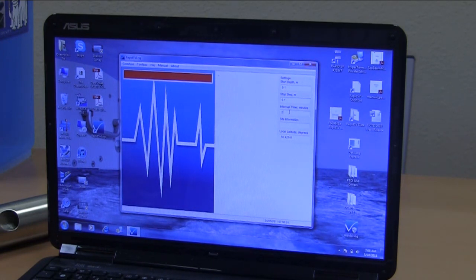Interrupt timer, that's the time the software waits between interrogations of the probe, and you'll get familiar with how to set this. Right now we're going to set it at 2 minutes. So the software will communicate with the probe, configure the probe, and it won't do anything to it until 2 minutes are up, which is essentially the time you've got to deploy the probe.